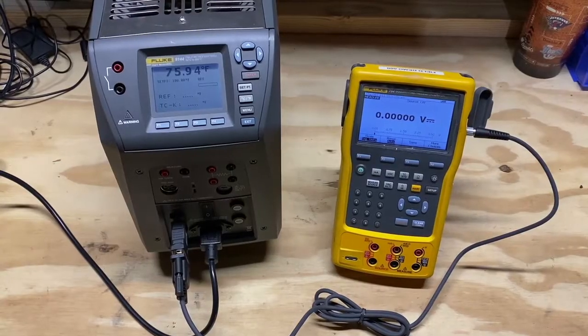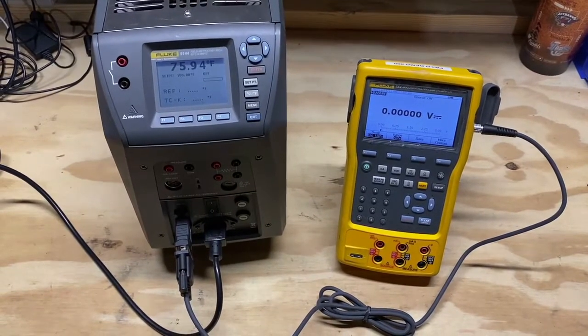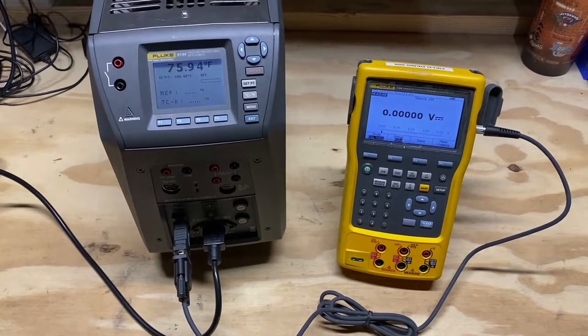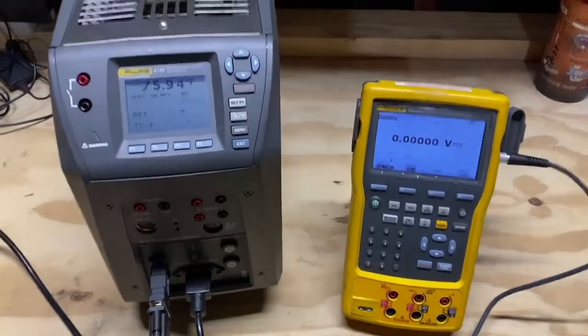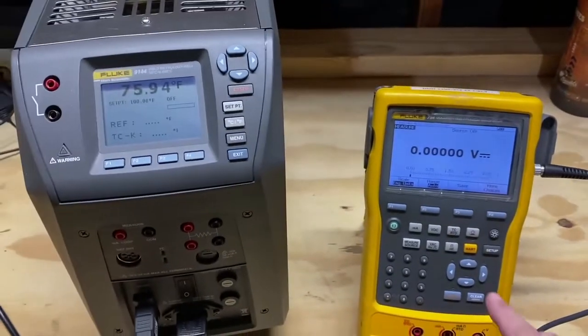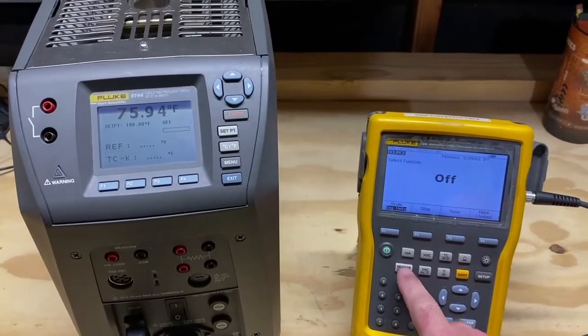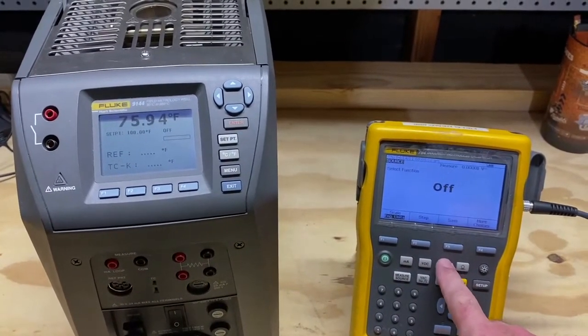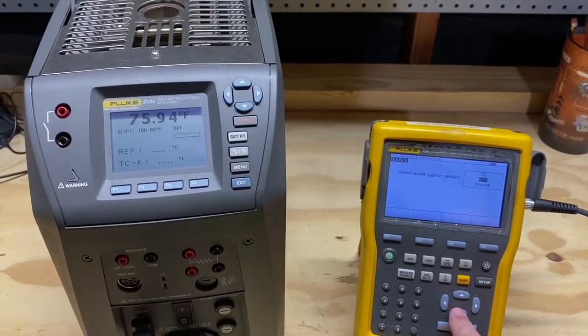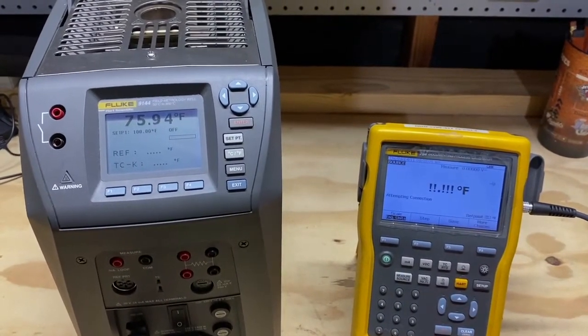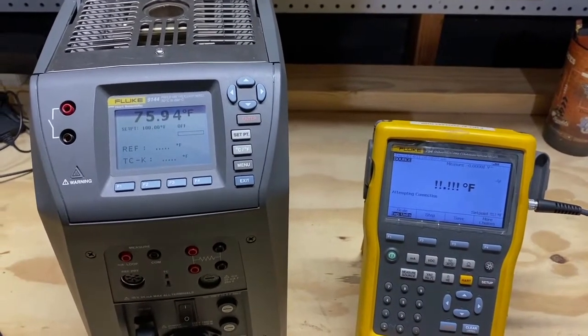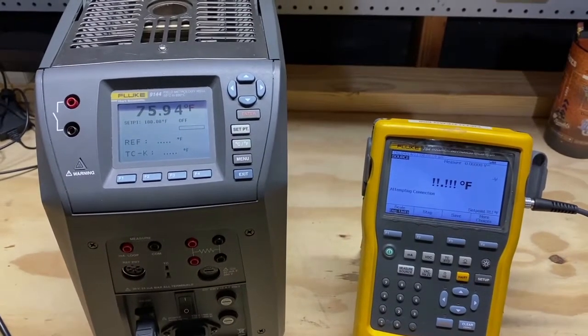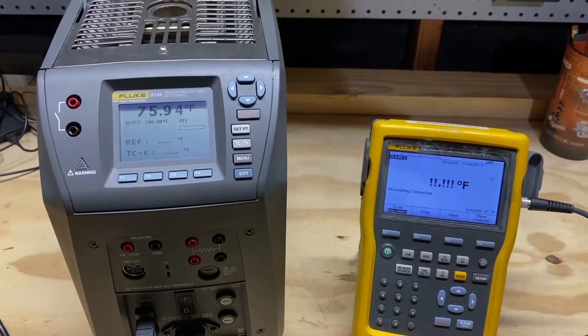After connecting the two tools together with the null modem cable, we will power them both up, go to the Fluke 754 source screen, select the temperature button, indicate dry well sourcing, and allow the 754 to connect to the 9144 in this example.